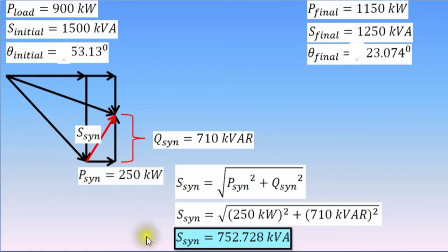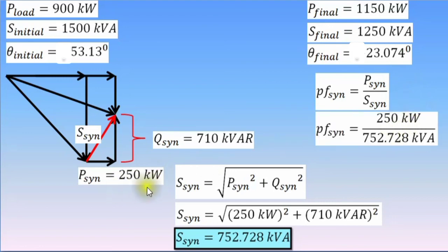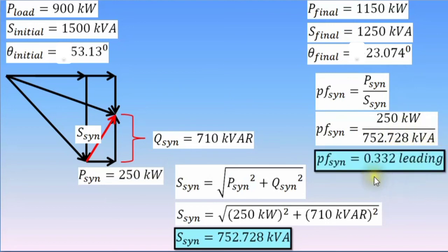Now that we have this value, we can now determine its power factor. Power factor, again, that is the ratio between the effective power and the apparent power. Substitute the values. 250 kilowatts divided by 752.728 kVA, this is equivalent to 0.332 leading. Again, the power factor of a synchronous motor is leading.